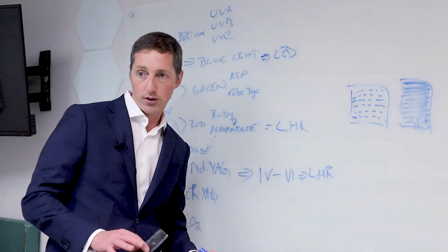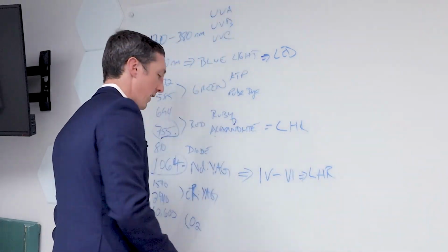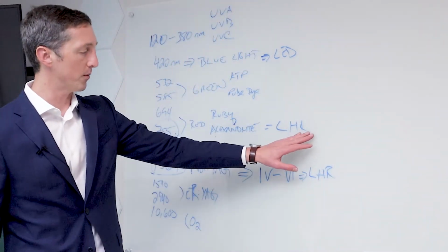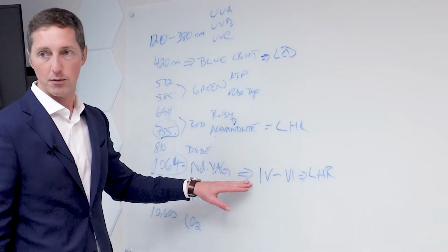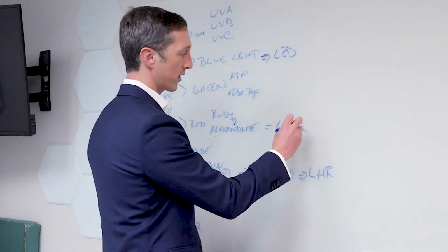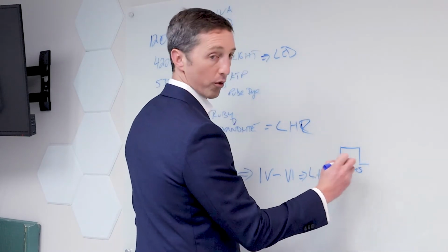photomechanical / photoacoustic, again the same thing, a little bit more so that you can get a visualization of what the difference is between our long pulse systems that we use for laser hair removal versus the exact same wavelengths of light that might be in what's called a short pulse or a Q-switch system. So let's say, for instance, that we're going to take this Alexandrite laser system and we're going to apply 10 joules of energy over 3 milliseconds, right?